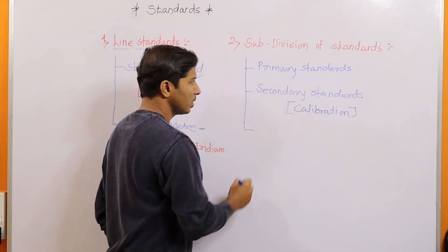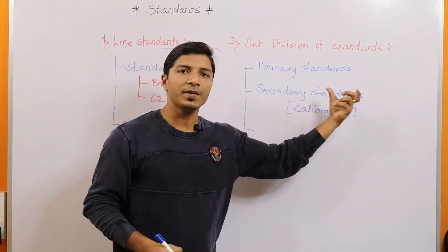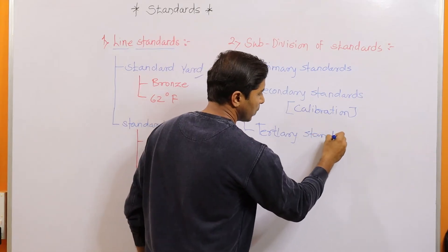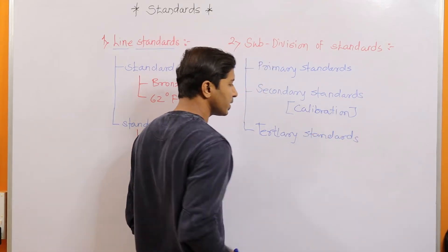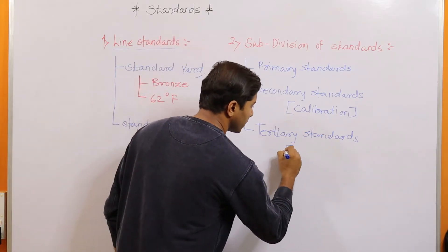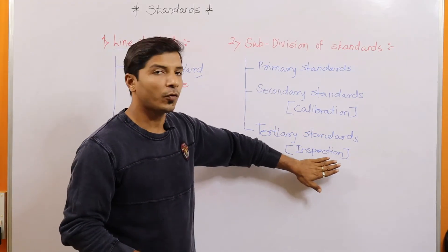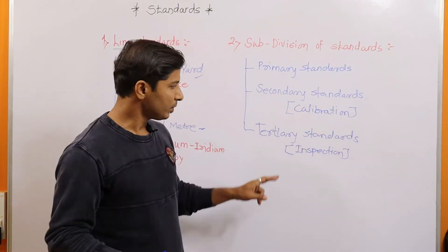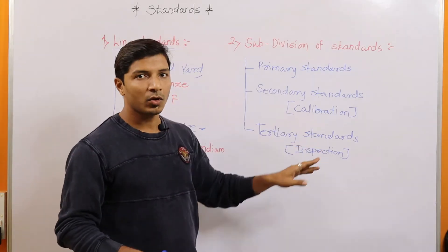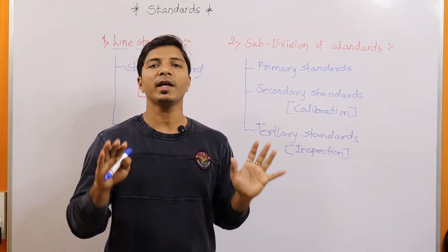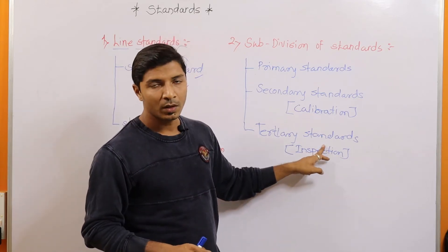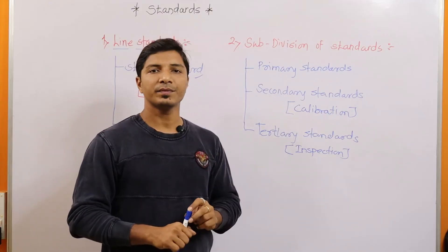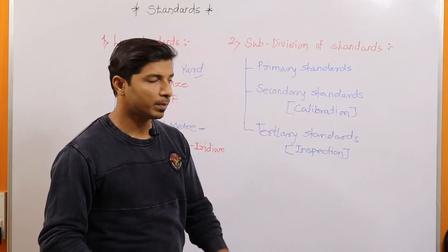By taking reference to secondary standards, tertiary standards are made. Tertiary standards can also be called inspection standards, as they are used for inspection purposes and can be frequently used in industries. Tertiary standards are not the instruments themselves, but at specific intervals they are used to check the accuracy of the working instruments.